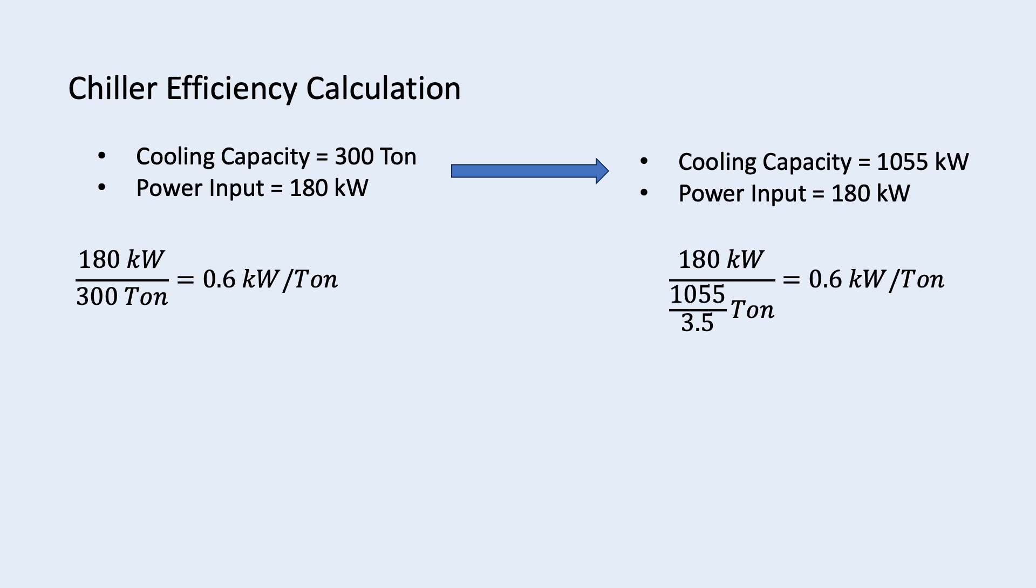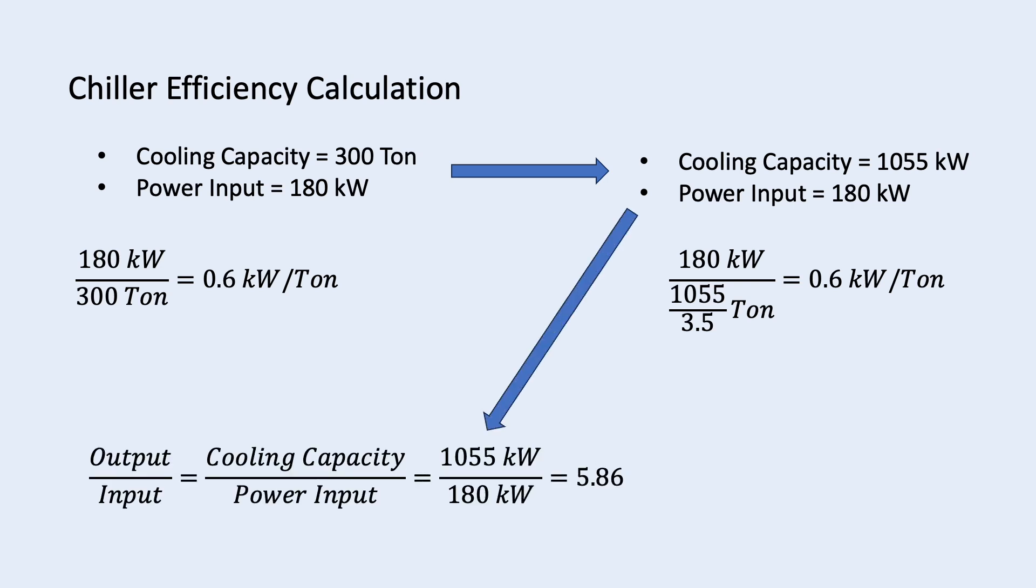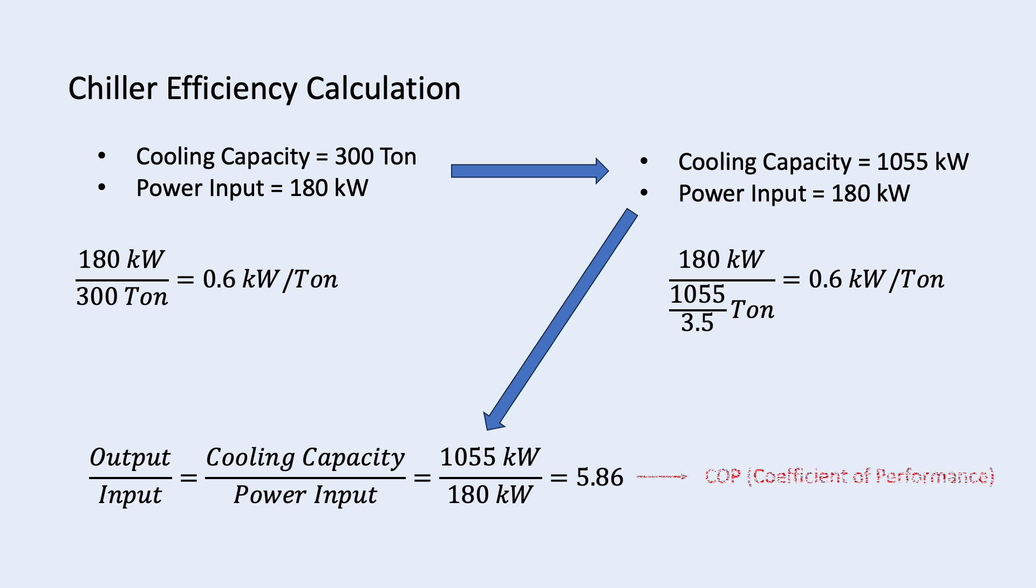But another way to calculate chiller efficiency just using kilowatt is by dividing the cooling capacity by the power input. 1055 kilowatt divided by 180 kilowatt equals to 5.86. And this is known as COP, coefficient of performance.